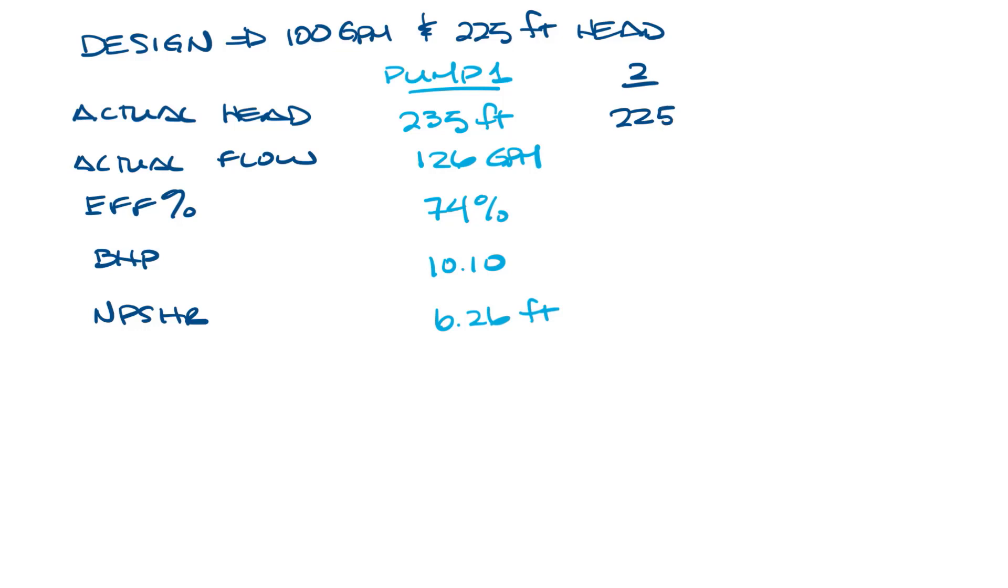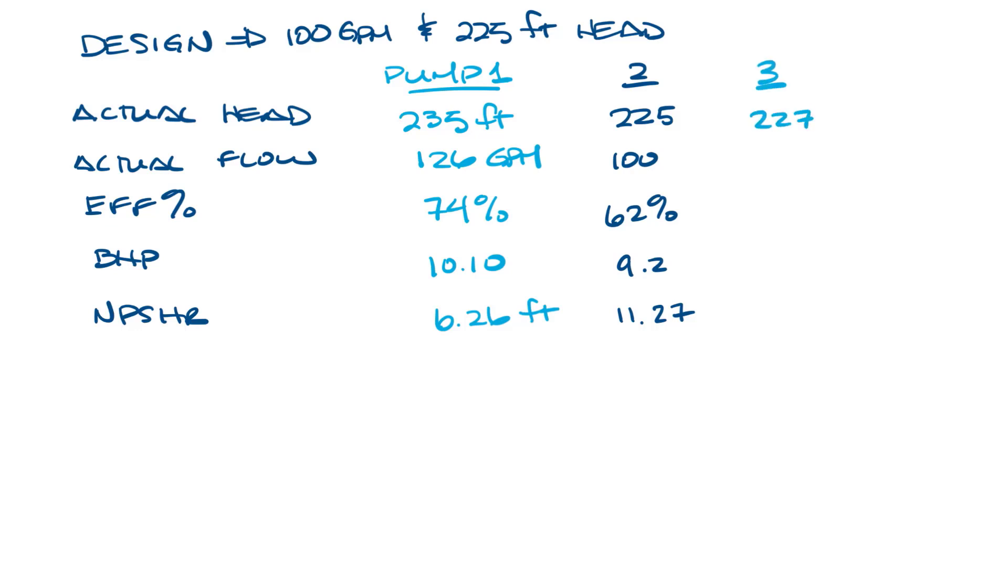The second pump was 225, 100, 62%, 9.2, and 11.27. Let's add a third and a fourth pump that we didn't see the curves on, but I'll put the performance here. So 227 feet of head, 100 GPM, 51% efficient, 11.1 horsepower, 6.6.